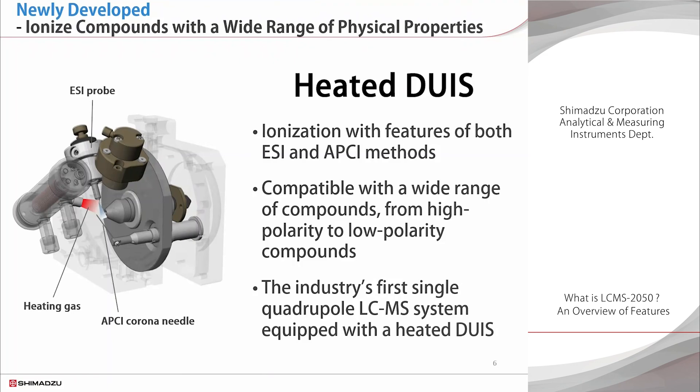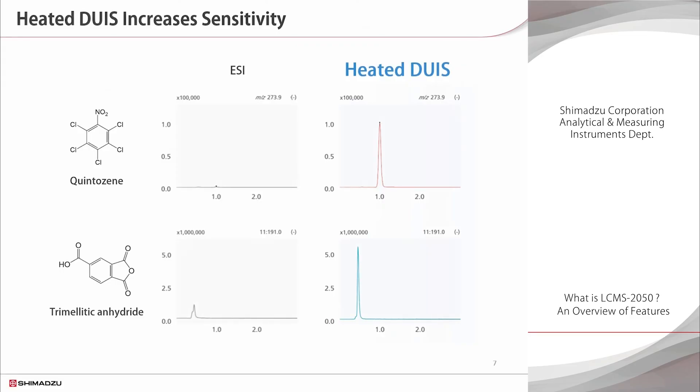This is the industry's first single-quadrupole LC-MS system equipped with a heated DUIS, or dual ion source. DUIS is ionization technology with the features of both the ESI and APCI methods. Compounds with a wide range of polarities can be analyzed at the same time, which leads to improved productivity. Comparing ESI and heated DUIS, the sensitivity is dramatically better when heated DUAS is used, significantly reducing the risk of undetectable compounds across a wide range of compounds.